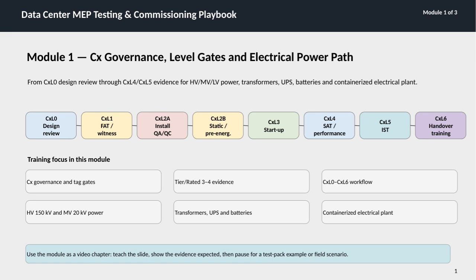You'll see the process broken down into key stages: design review, factory acceptance testing, installation quality checks, pre-energization static tests, startup, site acceptance testing, and finally, handover and training. Each stage plays a critical role in ensuring that electrical systems meet Tier 3 and Tier 4 standards for reliability and performance.